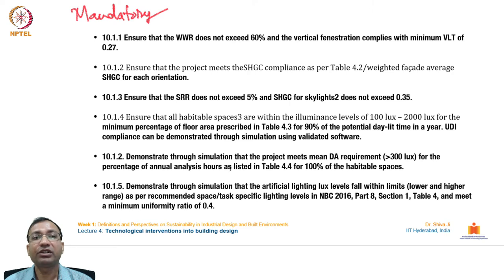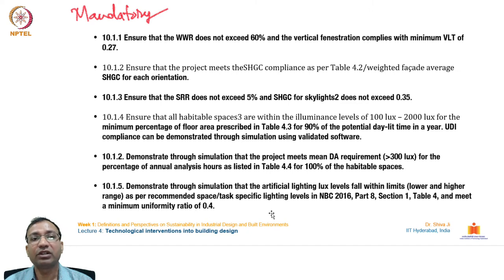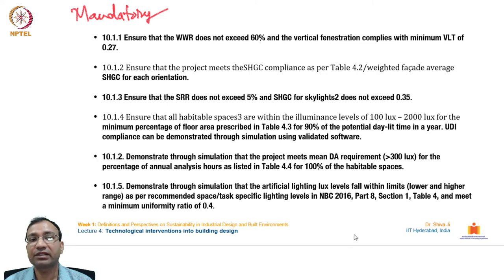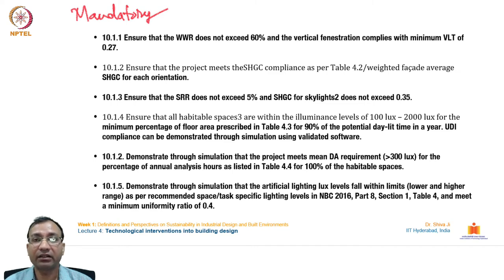Additional mandatory lighting requirements include: demonstrating through simulation that the project meets mean DA requirement of more than 300 lux for the prescribed percentage of annual analysis hours for 100% of habitable spaces; and demonstrating that artificial lighting levels fall within lower and higher range limits per NBC 2016 Part 8 Section 1 Table 4, with a minimum uniformity ratio of 0.4.